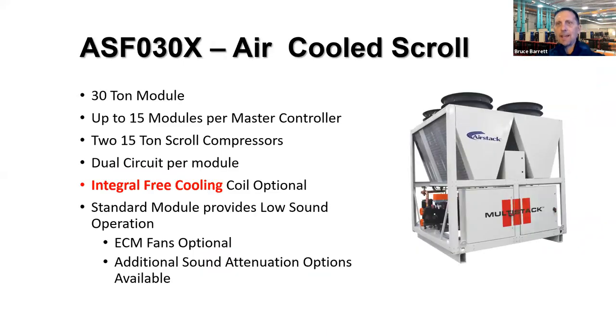All right, so that was our ASP, which is a mechanical module with independent free cools. The ASF is our latest design with integral free cooling as an option. It's only a 30-ton module. This design has really taken off quite a bit for 150-ton jobs and below that have critical cooling, are in locations, or have a temperature which is very good for free cooling opportunities. It is a dual circuit machine.